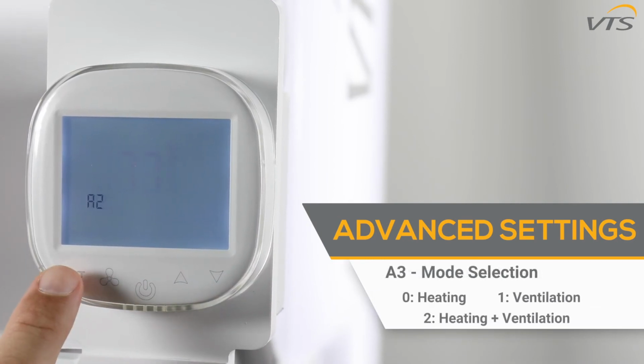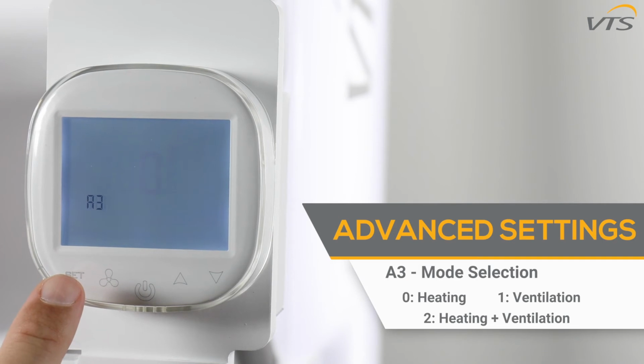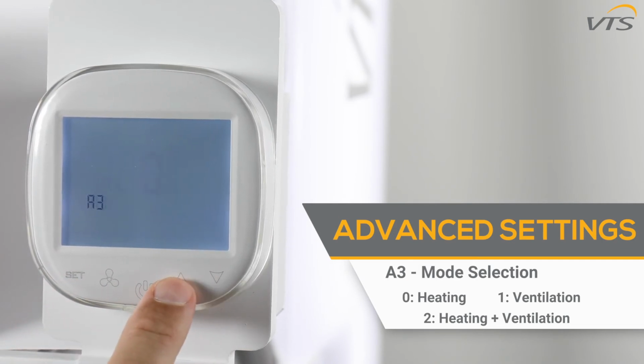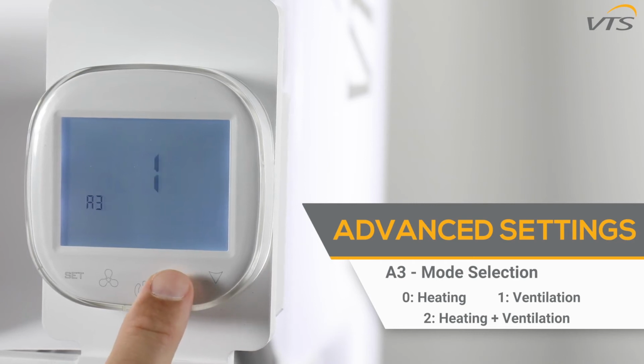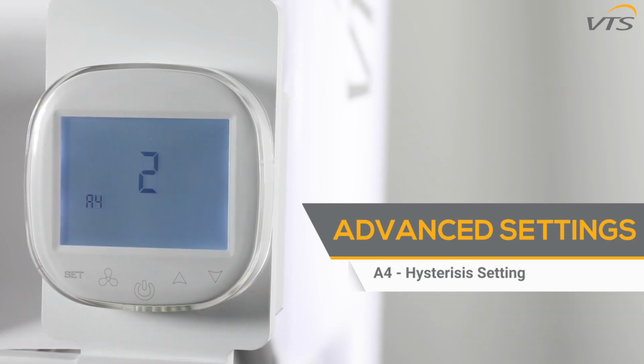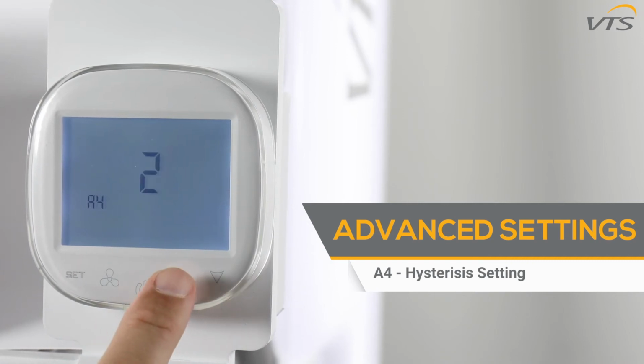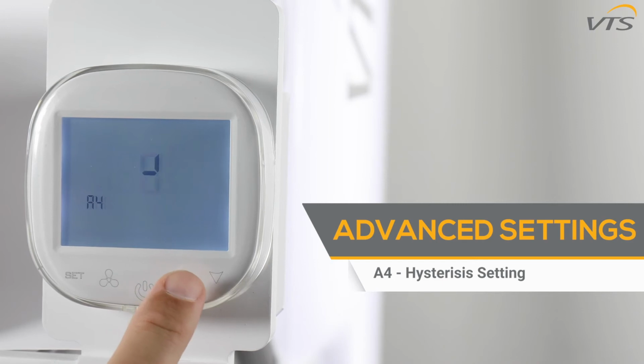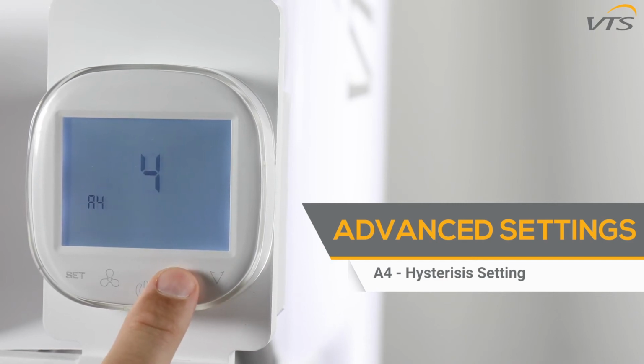The A3 function is used to select your mode. 0 means heating mode, 1 means ventilation mode, 2 means heating plus ventilation mode. The A4 function controls the hysteresis setting. This is the difference between your desired temperature and the room temperature after you've turned on the device. This is adjustable by degrees.